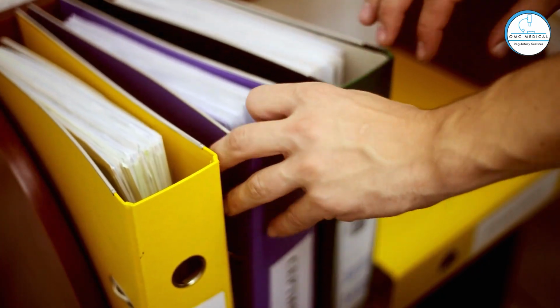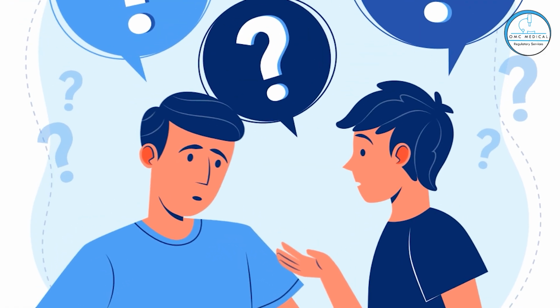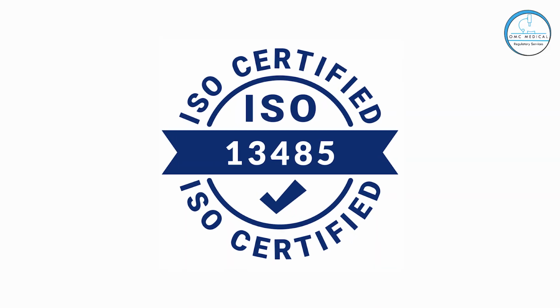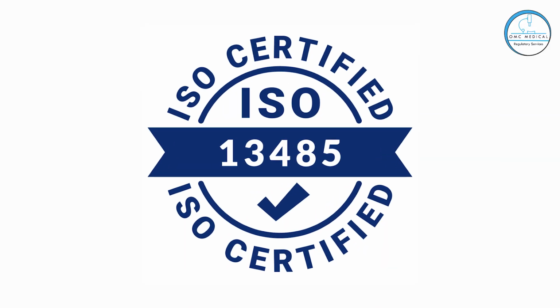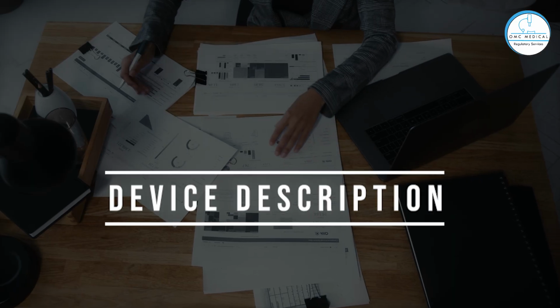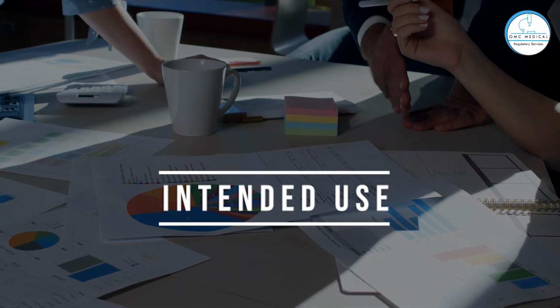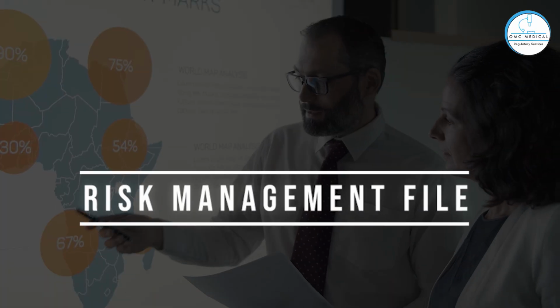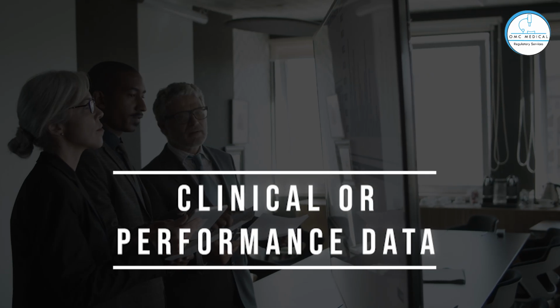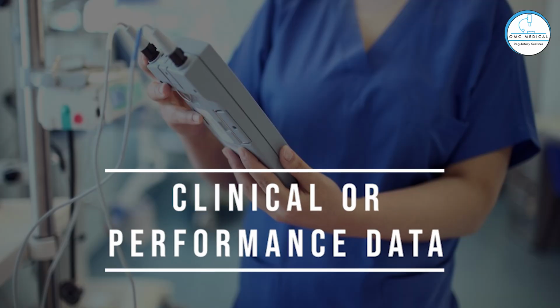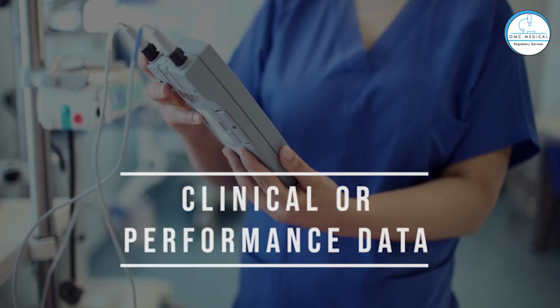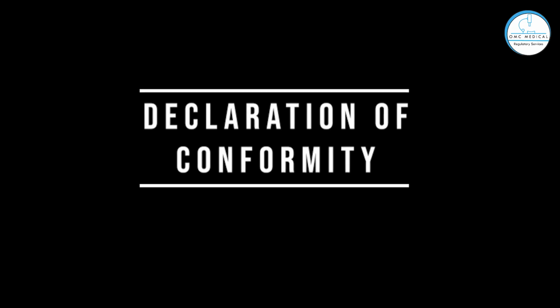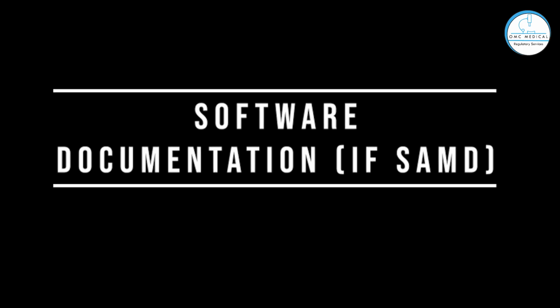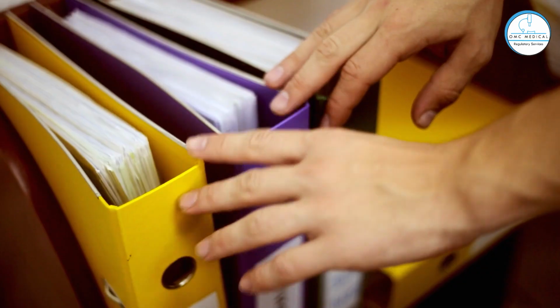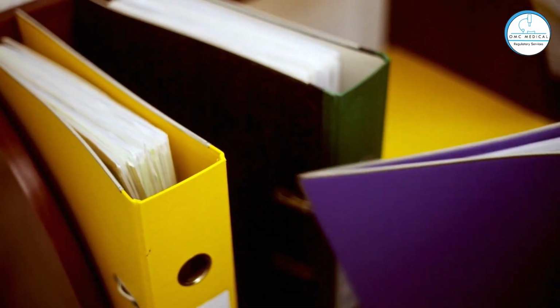Documents required. Here's what you'll typically need. ISO 13485 certificate, device description, intended use, risk management file, clinical or performance data, labeling and IFU, declaration of conformity. Software documentation if SaMD. Missing even one key document can delay your approval.